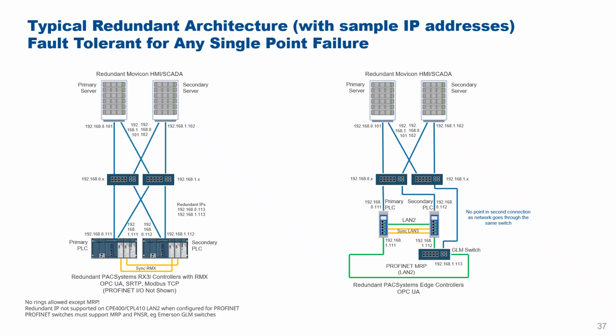I would argue though, why do you need a redundant LAN if you've already got redundant PLCs? Yeah, if you're looking at surviving any single point of failure, your first failure, if it's on the first LAN, provided you don't have a single point of failure with your network switch, then it would be feasible to say, well, I will just have one connection, and then if that connection fails, my secondary PLC will take over. But yeah, you could argue then that there is a single point of failure there, which is the switch itself. So unless you've got some sort of redundant switch arrangement, that secondary LAN arrangement does give you that additional level of fault tolerance. So as I say, a bit more complicated to set up with Profinet, because Profinet rings don't necessarily work well with redundant networks. But by doing it in this way, with this architecture on the right, this does allow you to have full fault tolerance for any single point of failure.